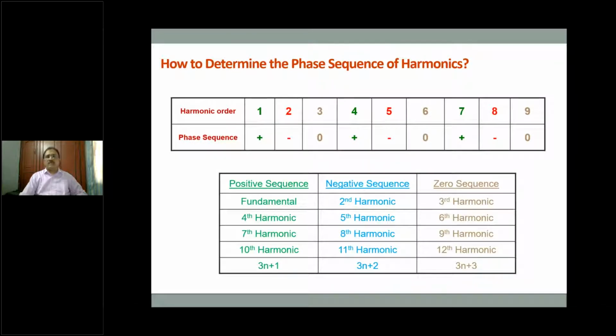So how do we understand the sequence of harmonics? If any one of you is going to discuss harmonics in any class or any industry area, we will have to understand how these harmonics are sequenced. So the first order harmonic is called the fundamental harmonic. Second is even, therefore it will not be counted. Like I told you, even numbers are not counted. It is a negative sequence harmonic, but not measured or counted.